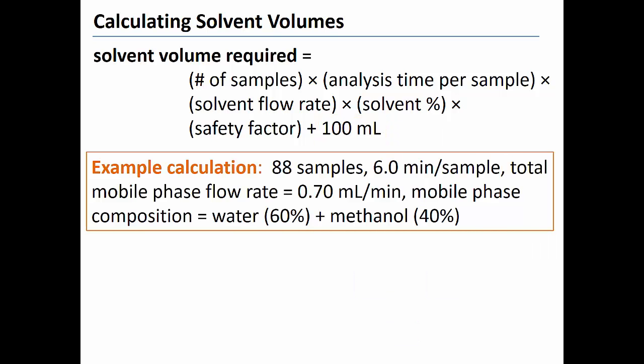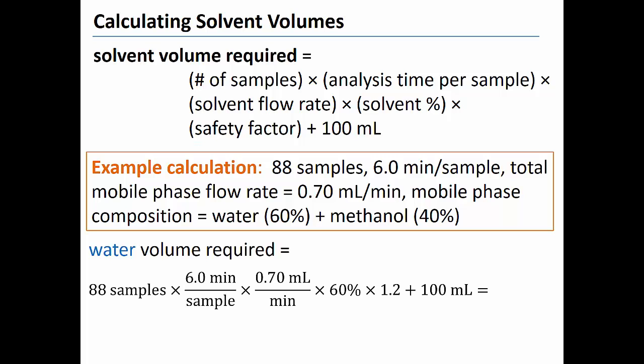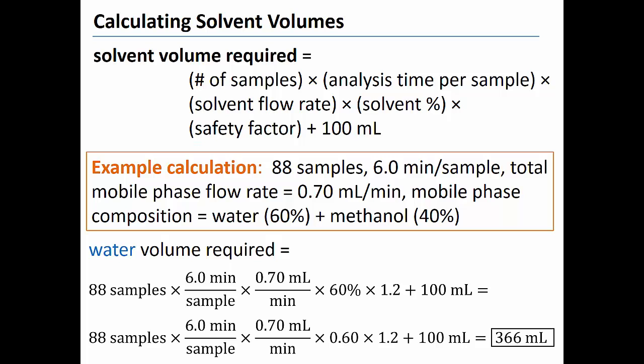If a user wants to analyze a batch of 88 samples, each injected one time, using a method that requires six minutes of analysis time per sample, a total mobile phase flow rate of 0.7 milliliters per minute, and a mobile phase that is fixed at 60% water and 40% methanol, we can use the equation shown above to estimate the needed volume of water and methanol. Let's begin by calculating the volume of water required. We can insert the given values into our equation. The equation predicts that we will need to begin the analysis with at least 366 milliliters of water in the water bottle.